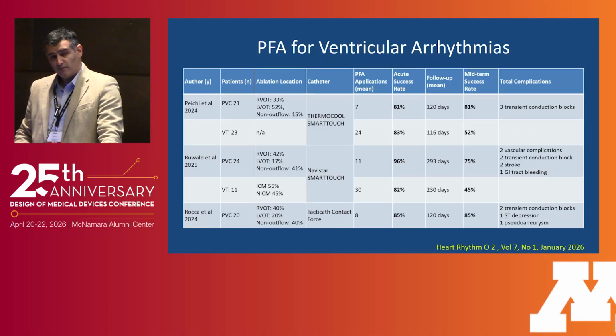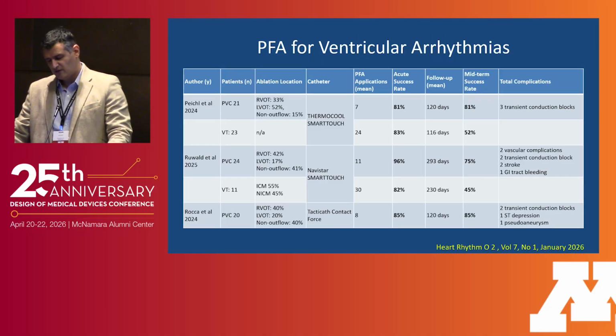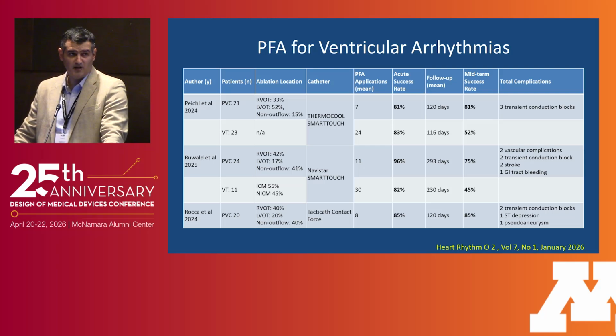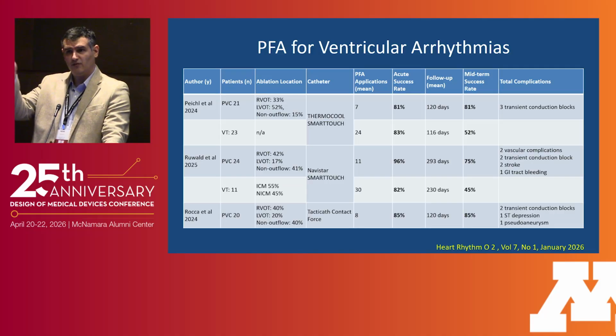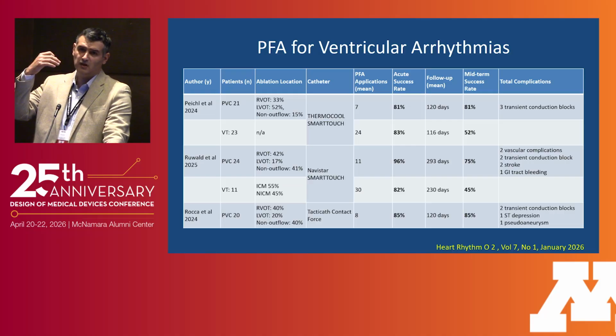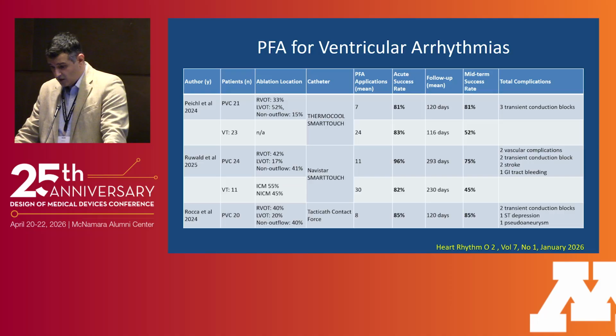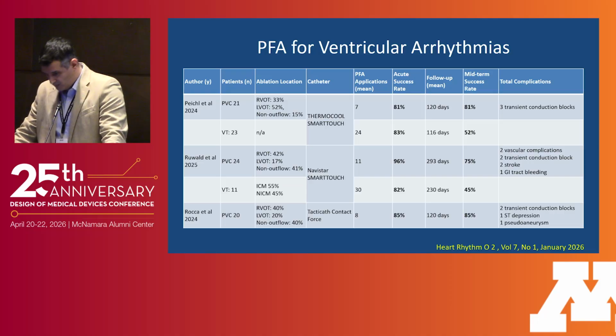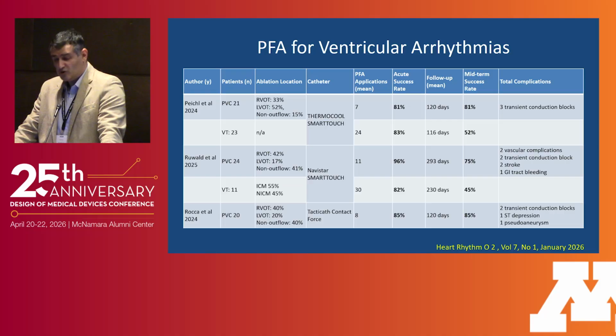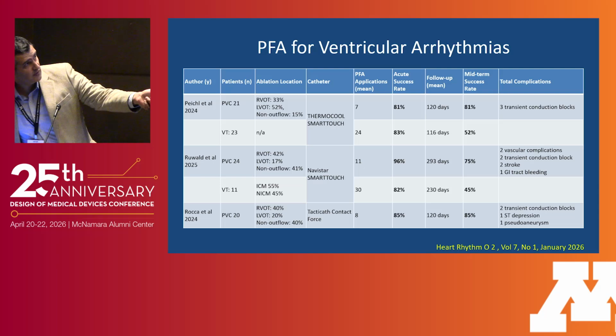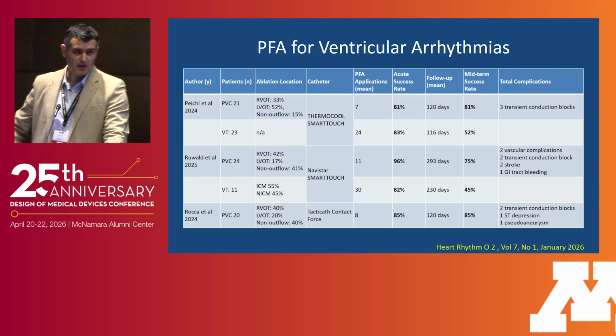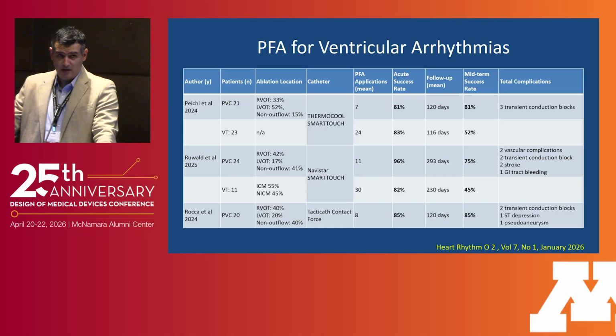So that was followed by 3 main studies that looked into VT ablation and PVC ablation using PFA. The first one was with a ThermoCool catheter from Biosense Webster, the same as the RF catheter that we used before. It was modified to be able to deliver both PFA and RF. Acute success was reasonable, in the 80% range. The problem with this, especially for PVCs acutely, is the high recurrence rate, especially with VTs later on. So they achieved reversible electroporation and not irreversible, which is what you really want.